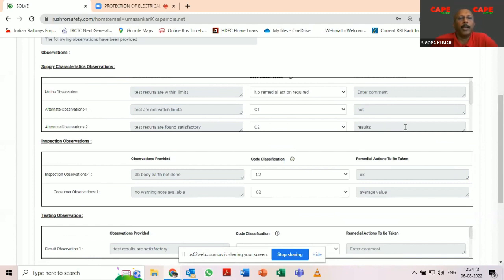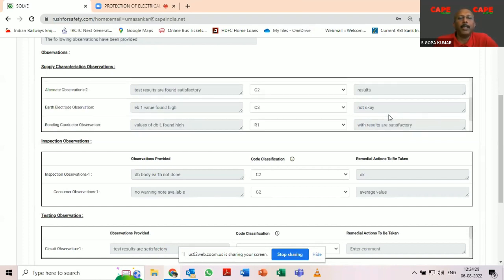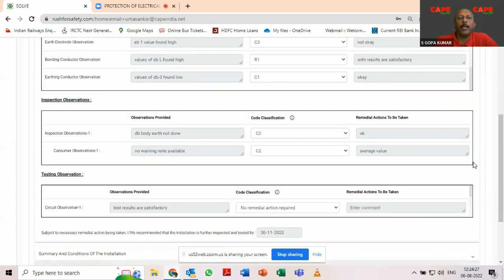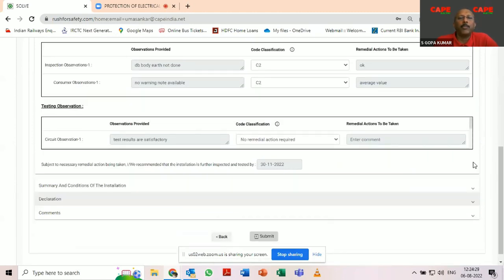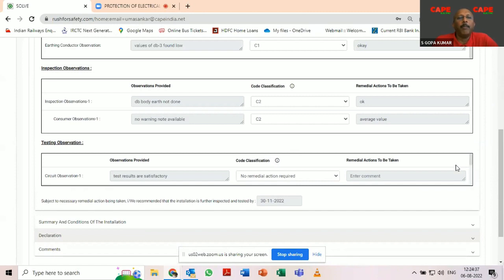Then you check these parameters like its protective bonding, its disconnection time, its insulation resistance, and so on. So basically, not only the electrical installation, the safety parameters of the entire connected load is also included as modules, so that the software gives you a very good opportunity to find out whether your electrical installation is in good shape or not.